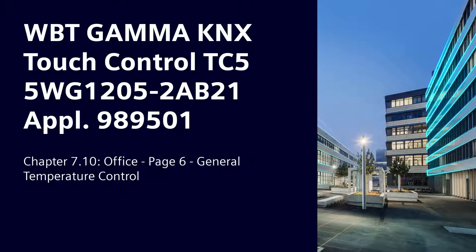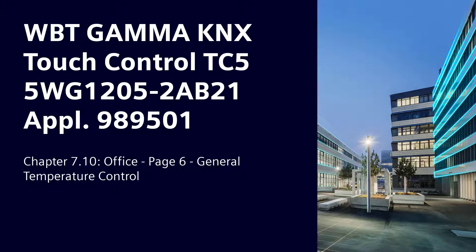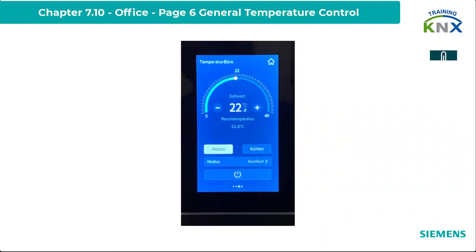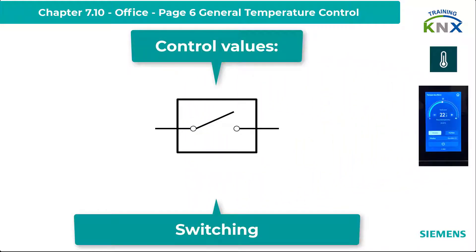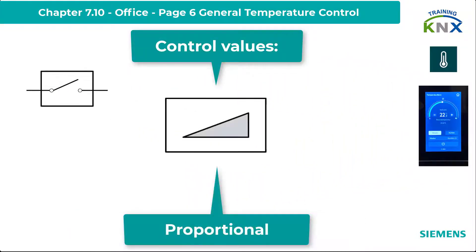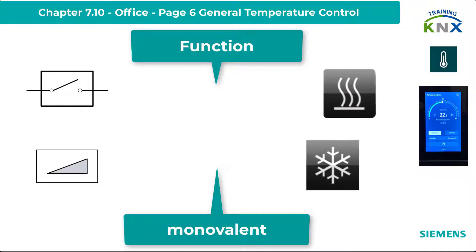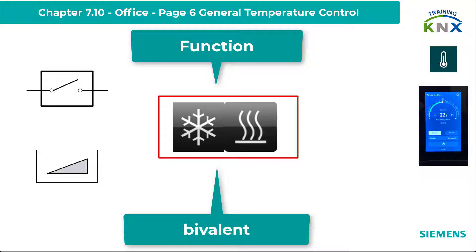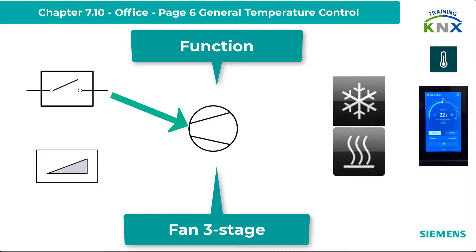Chapter 7.10: Siemens Gamma KNX Touch Control TC5 - General Temperature Control. The General Temperature Controller of the TC5 handles the usual control options: switching or proportional control variables, monovalent (only heating or only cooling) and bivalent (both options available), up to 3-stage fan control, and 1-bit or 1-byte control variables.